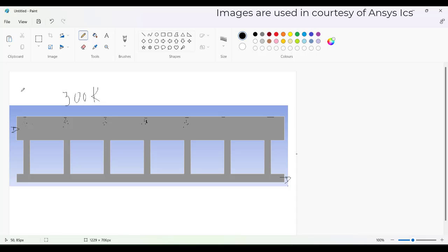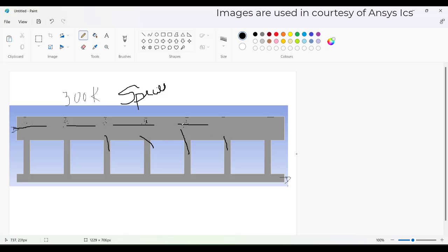So as hot air — which is a combination of water vapor, nitrogen, and oxygen, so it is a species — a species which has all these species together will be used for our simulation. When it is going in this direction, it will divide into different passages and come across these droplets where heat transfer will occur. Some amount of liquid water, in the format of a droplet, will start evaporating by taking heat from the air, so the temperature of the air will be reduced. The initial temperature of the air will be around 360 Kelvin. As it passes through the 300 Kelvin water droplets, obviously the temperature will drop, and the water will take that heat and in turn will turn into vapor.